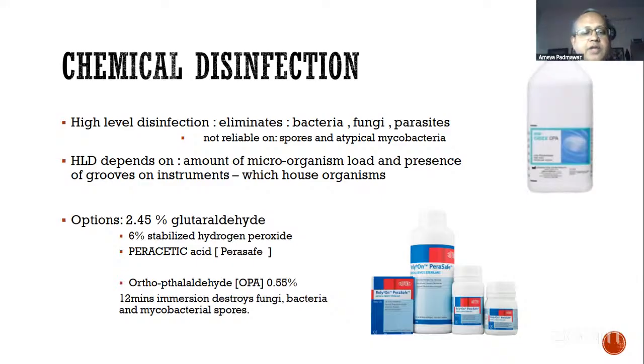Then you have peracetic acid, also known as Perasafe, in which you are using a reconstituted solution using this peracetic acid, which comes in a powder form. So for people who are going from one center to another, this is a very good boon. And the activated solution can be used for 24 hours. Again, immersion time is at least 10 minutes. For glutaraldehyde, it is at least 20 minutes. And for total sterilization, means if you want to get rid of the atypical mycobacteria, the immersion time is at least 60 minutes. That is 1 hour.